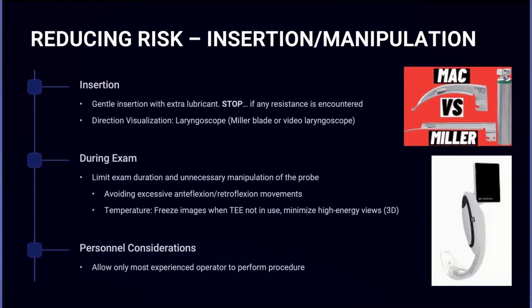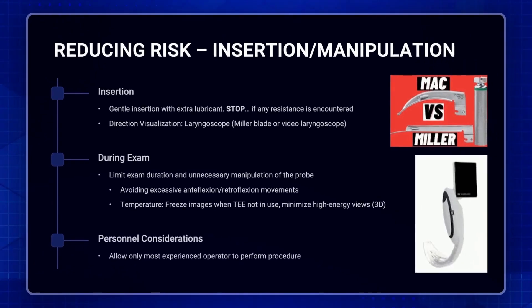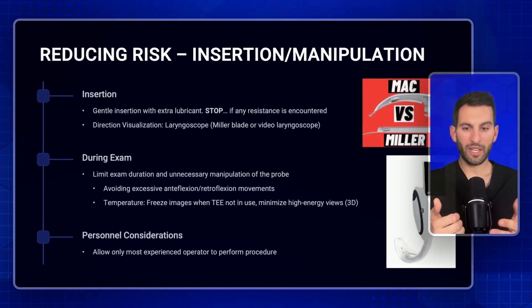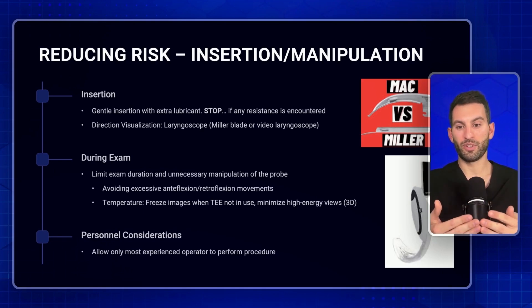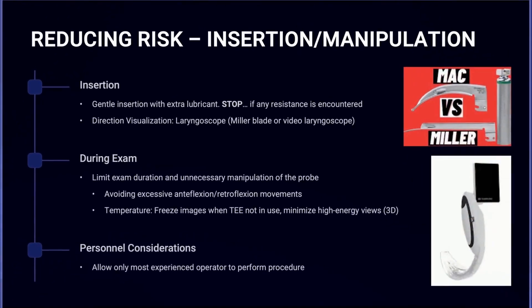During the actual exam, limit any unnecessary duration or manipulation of the probe. Only image what you have to image. Avoid excessive anteflexion or retroflexion. Avoid keeping the probe in locked positions for prolonged periods. Also, freeze your images when the TEE probe is not in use and minimize high-energy views like 3D, as these can increase the temperature of the TEE probe.